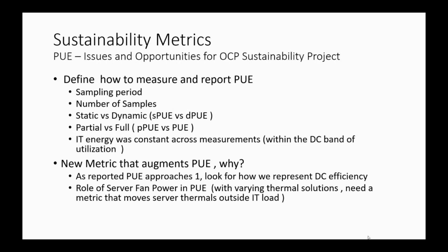And the other one is, what a server is, is undergoing redefinition, right? So for example, you go to immersion cooling or you go to liquid cooling. The role of server fans changes substantially in presence of those types of thermal solutions. Now, what's inside the data center boundary and what's inside the IT boundary, if that is changing, then you need to comprehend that change, because PUE was defined in the good old days of, like I said, more than 10, 15 years ago, when it was very clean.